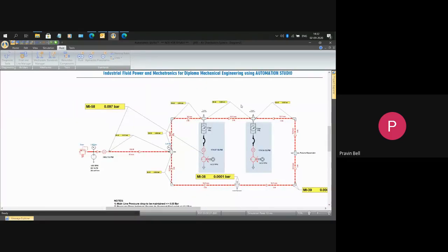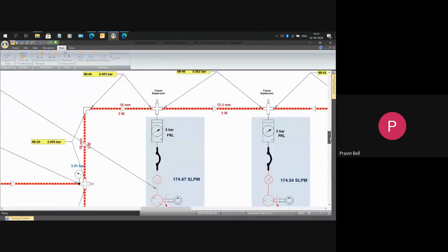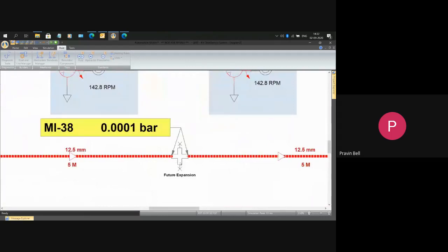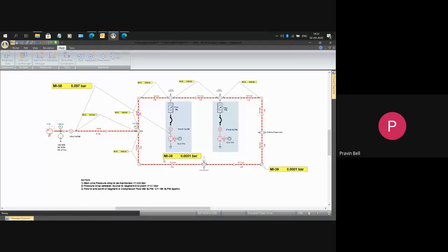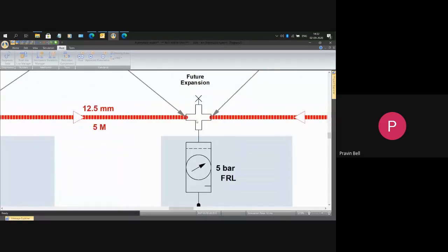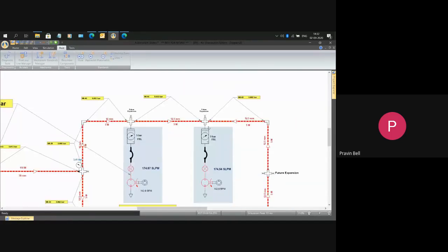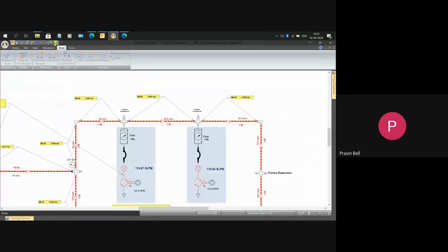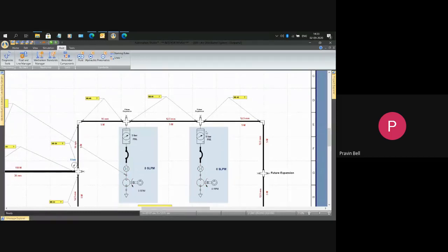Then obviously you can see the pressure drops across the other fittings here. So in this way, you can play around with all the line segments, the fittings, the diameters, lengths, and you can actually build the entire air distribution system. The software also does nice things. For example, at this point, you can see the air is coming from both sides, left and right, because the air demand here is higher. So the software does this very beautiful animation and simulation also. Okay, so very easily built.